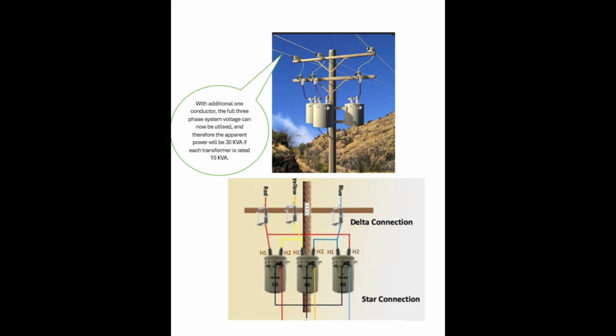With an additional 1 conductor, the full three-phase system voltage can now be utilized, and therefore the apparent power will be 30 kVA if each transformer is rated 10 kVA. This justifies the limited rating of open delta with 17.3 kVA. With just 1 additional conductor, the extra 12 kVA was achieved. The advantage of using 3 single-phase transformers connected in this fashion is that in case of failure of 1 transformer, the open bank connection can be used as shown in the previous image.